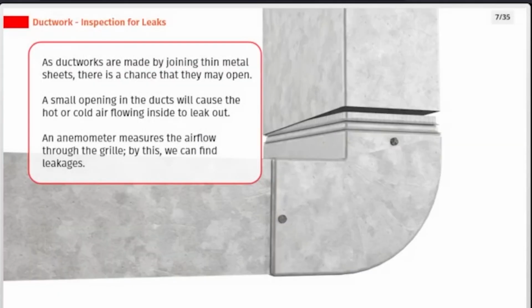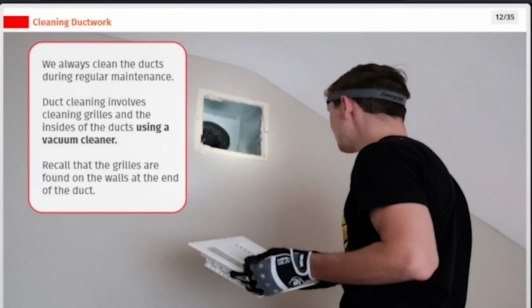As ductworks are made by joining thin metal sheets, there is a chance that they may open. A small opening in the ducts will cause the hot or cold air flowing inside to leak out. An anemometer measures the airflow through the grill. By this, we can find leakages. We always clean the ducts during regular maintenance. Duct cleaning involves cleaning grills and the insides of the ducts using a vacuum cleaner. Recall that the grills are found on the walls at the end of the duct.